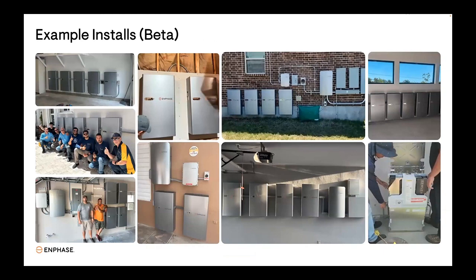Okay, here are just a couple of photos since we just talked about the dimensions of the battery, so you can see how it can be installed. If the batteries are installed next to each other, they can be installed as close as 4 inches together. And they can be installed above and below each other as well, as you can see in the bottom left-hand corner, with a 6-inch space between the batteries to allow for enough airflow for cooling.